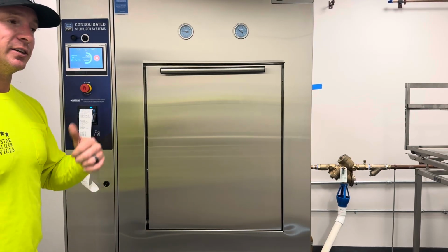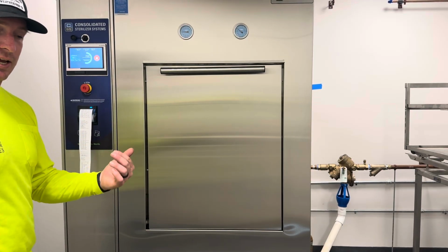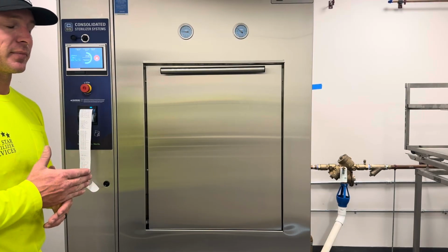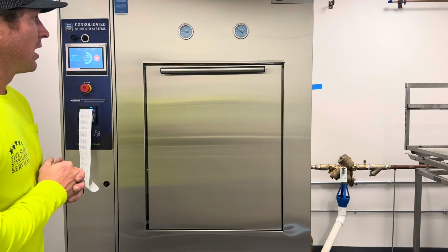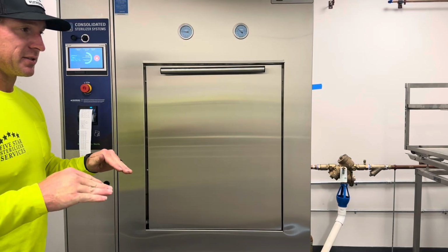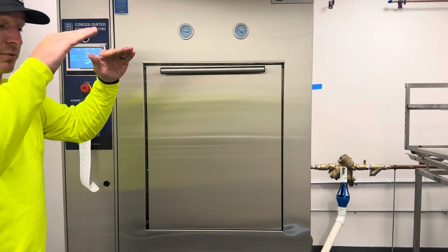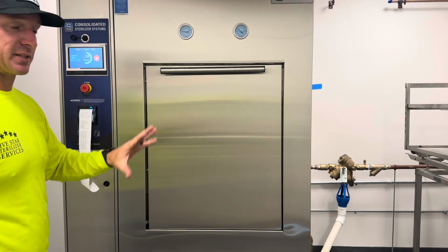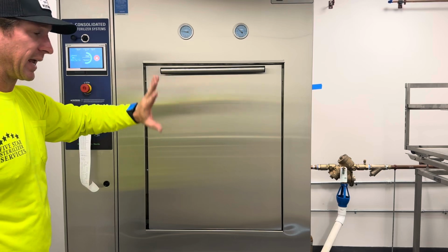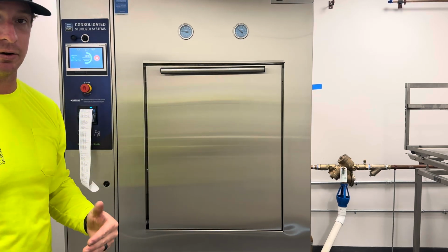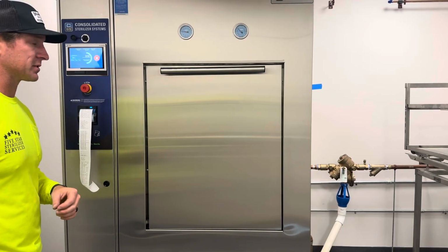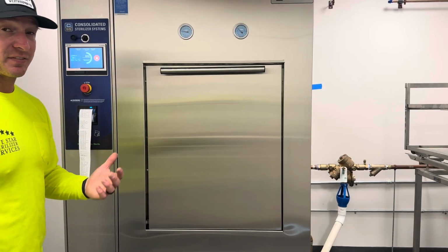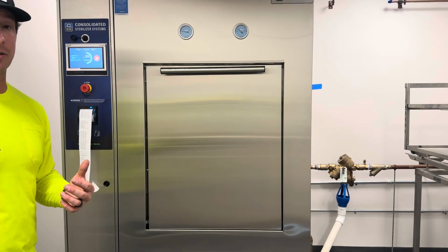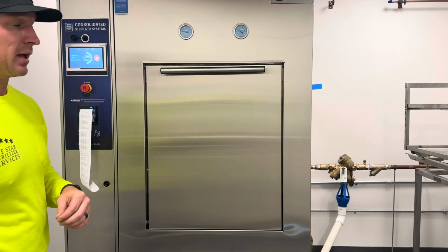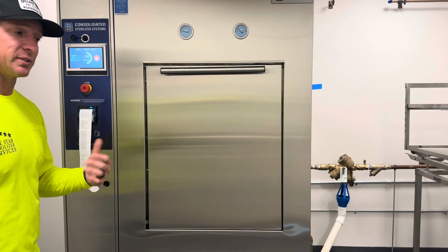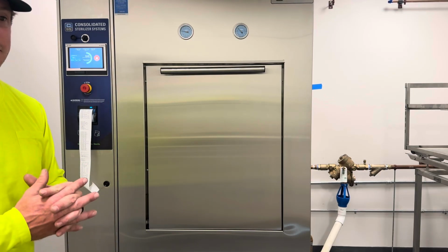On a liquid cycle, nobody has control over how long it takes because that's a preset time for the liquid cycles to exhaust. On liquid cycles, we want to bring things up at a slow, even pace, but also bring them back down at a slow, even pace. That's why it's preset for the exhaust. You cannot alter that. Plus, there's a 10-minute cool down on the backside of a liquid cycle. You can estimate if you're going to run a 15-minute liquid cycle, it's probably going to take about 45 minutes to an hour to complete. Whereas if you ran a 15-minute gravity cycle, the total estimated cycle time would be maybe 19 to 20 minutes.